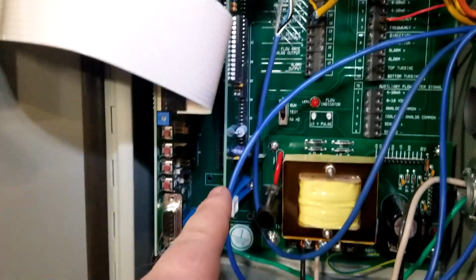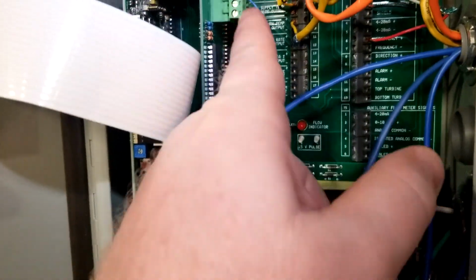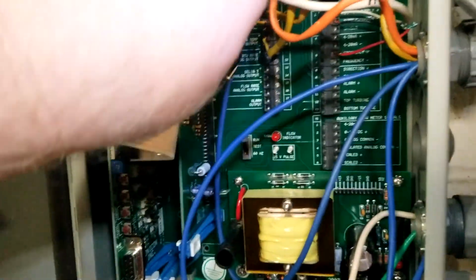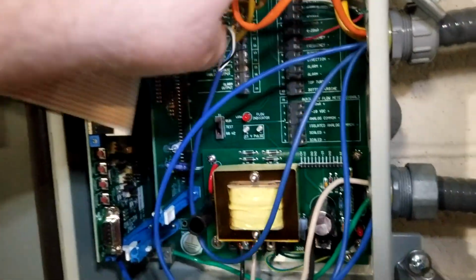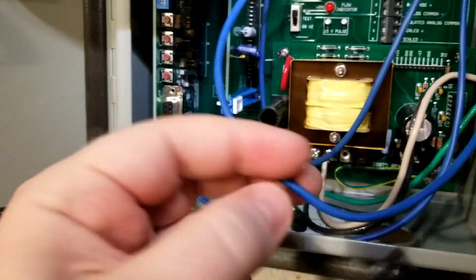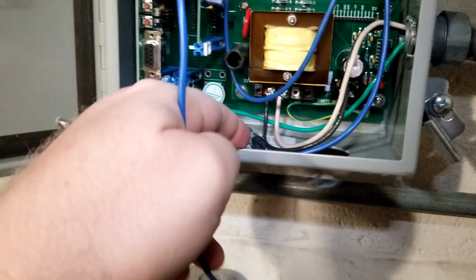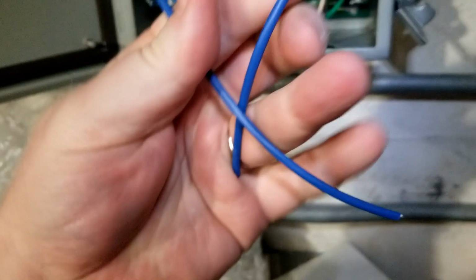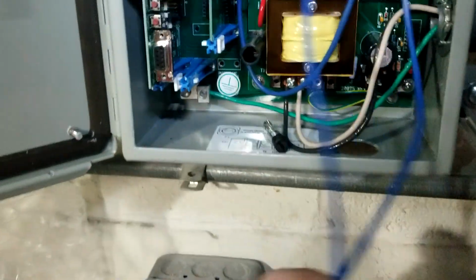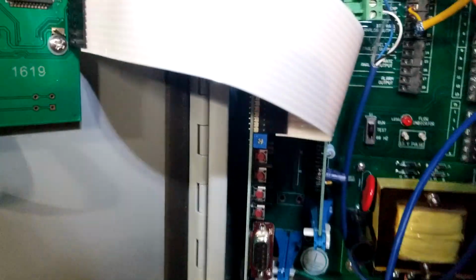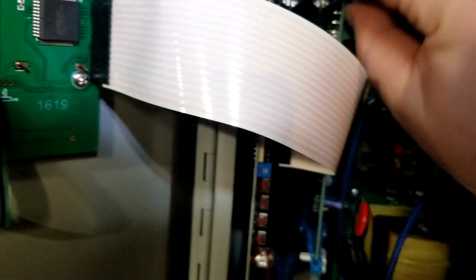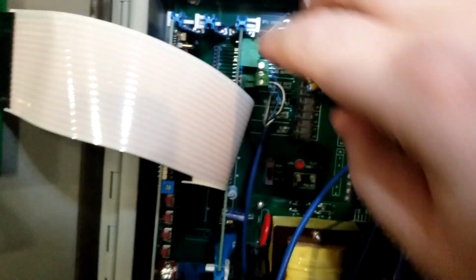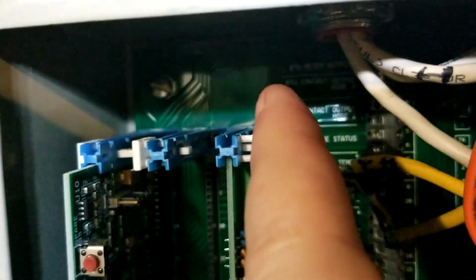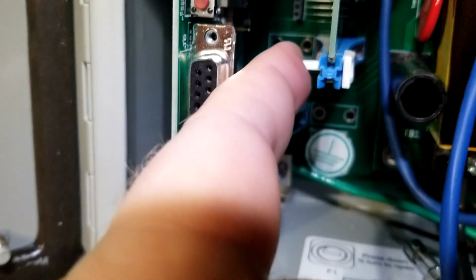The next thing we're going to do is swap the communication card on the Onicon flow meter. This is the communication card here, and you can see our N2 trunk here. I'm going to unplug this trunk. I need to make up the connections for the new trunk, which is these two wires here — we'll do that in just a moment. Once I get this done, there are tabs here I can press over; you can see how I move this one over to the right, and this one here, you can see it.